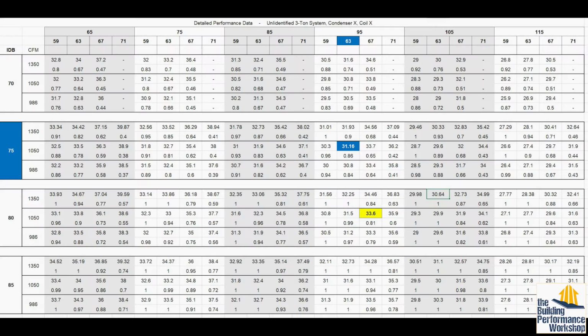I've got a little cheat sheet down here—where did I put it? There it is. So I've got a 3-ton unit's data here. It's a ton of data, an intimidating amount of data. There's this little yellow box I put on there, and that box is AHRI. AHRI gives me one little data point, and the actual performance of the system is dozens of data points. AHRI is picking an outdoor temperature, an indoor temperature, an indoor humidity, and a CFM to test their systems.